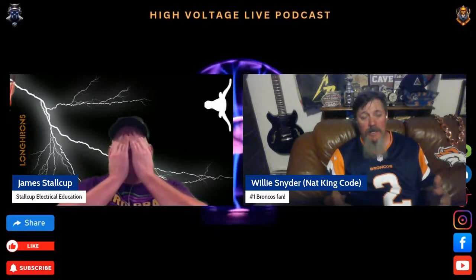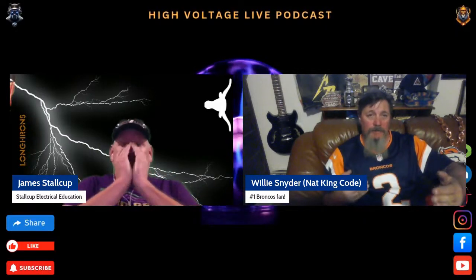We were just joking. I sent the picture to the 70E group and said, hey, we just found our medium voltage tester. Kind of threw Lemonhead under the bus a little bit, and here I'm being a bus driver. But I threw Lemonhead under the bus, and I said he was our new medium voltage guy for testing medium voltage. And it is legal to test for the presence of medium voltage at a 5 foot distance, because you're not entering the restricted approach boundary.